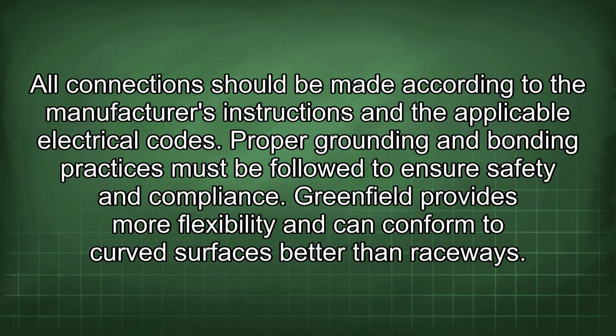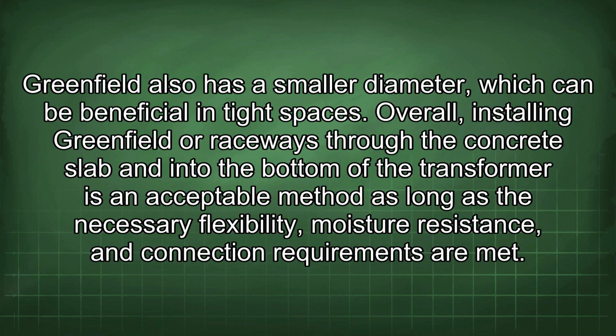All connections should be made according to the manufacturer's instructions and the applicable electrical codes. Proper grounding and bonding practices must be followed to ensure safety and compliance. Greenfield provides more flexibility and can conform to curved surfaces better than raceways. Greenfield also has a smaller diameter, which can be beneficial in tight spaces.